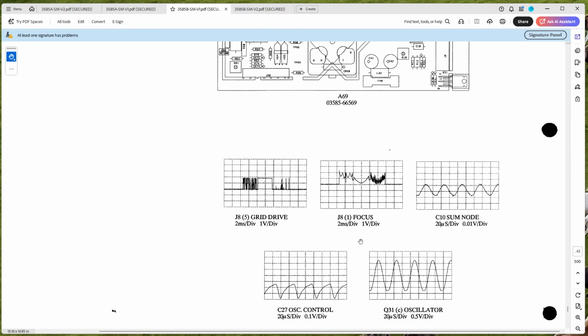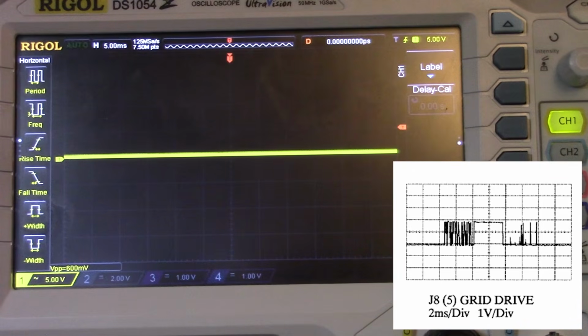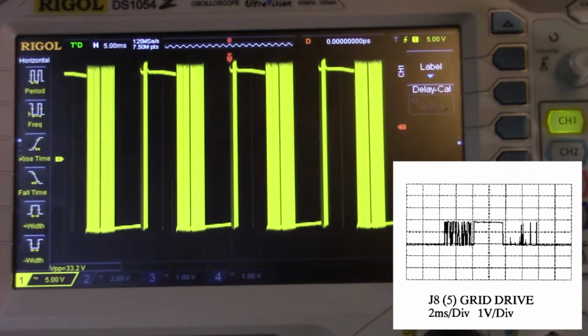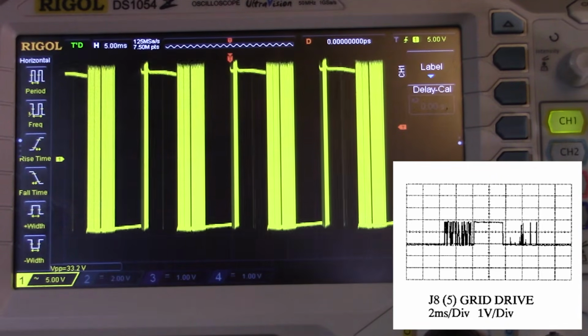So the grid drive and the focus signal should at least look like that. So let's take a look at the grid drive. I'm just going to take that off. Let's get our probe in, and we'll hook that onto pin 5 there. And then we'll turn this on. Okay. So now what it says is 2 milliseconds per division, 1 volt per division. And so the grid drive, according to that, should be 2 volts. Okay. So that does not look correct.